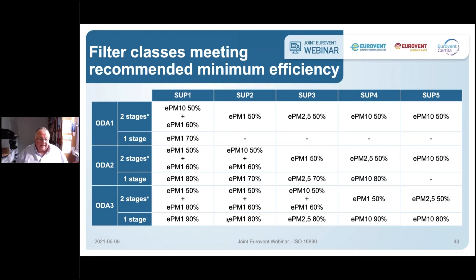If we have, for example, here outdoor air quality 2, and we want to have supply air quality 1 for pharmaceutical pre-filtration, then we have here an EPM1 50% filter and an EPM1 60% filter. So I think that's pretty clear how to choose the filter, and that should be specified: I need either a two-stage filtration with these efficient filters, or a one-stage filtration, but then the filter has to have a higher efficiency here of EPM1 80%.